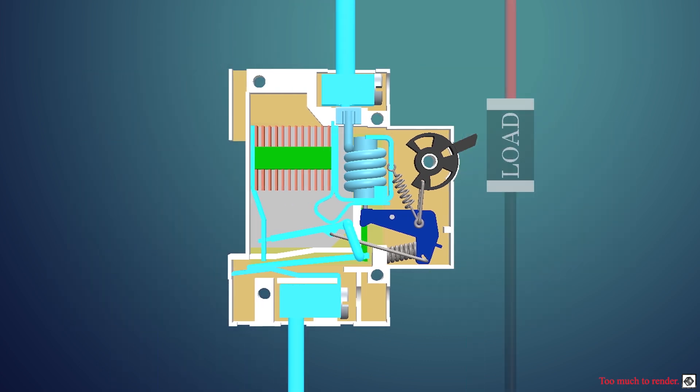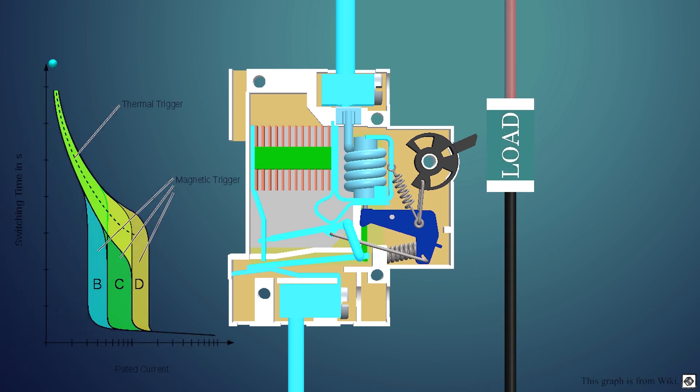First, we will see the overload situation. When the MCB is on, the current flows through the bimetallic strip, and thus the strip starts bending. Its bending depends on how the strip is manufactured, so different strips bend by different amounts for the same current. Also, the bending of the strip depends upon the heat generated by the current through it.